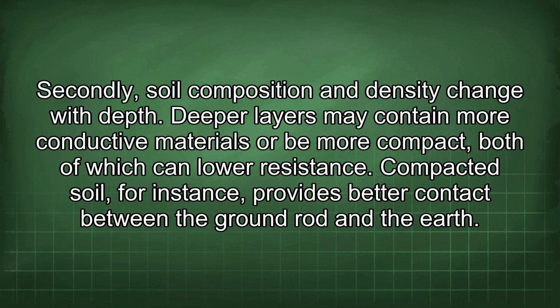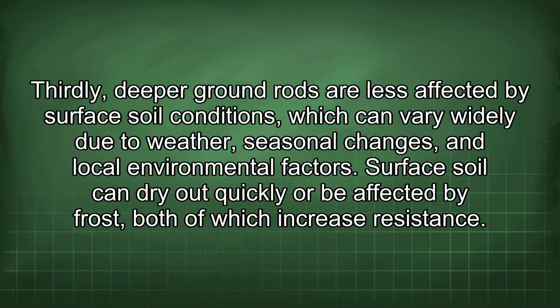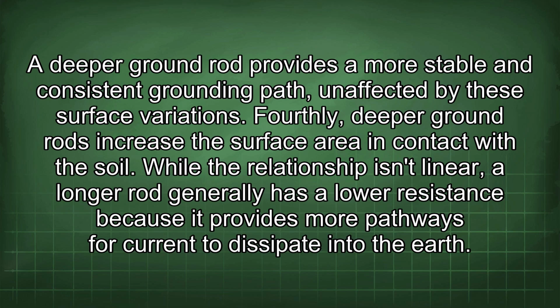Secondly, soil composition and density change with depth. Deeper layers may contain more conductive materials or be more compact, both of which can lower resistance. Compacted soil, for instance, provides better contact between the ground rod and the earth. Thirdly, deeper ground rods are less affected by surface soil conditions, which can vary widely due to weather, seasonal changes, and local environmental factors. Surface soil can dry out quickly or be affected by frost, both of which increase resistance. A deeper ground rod provides a more stable and consistent grounding path, unaffected by these surface variations.